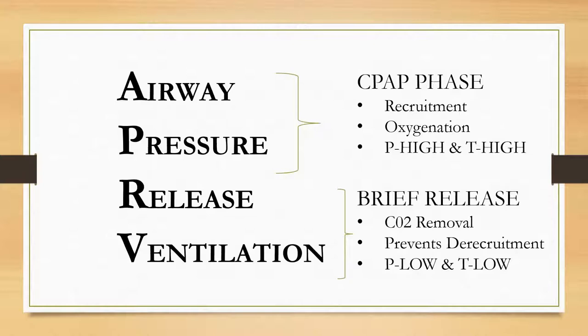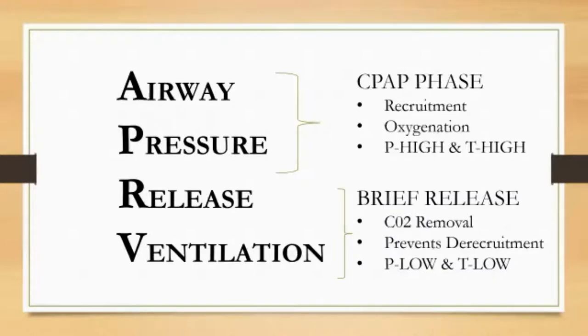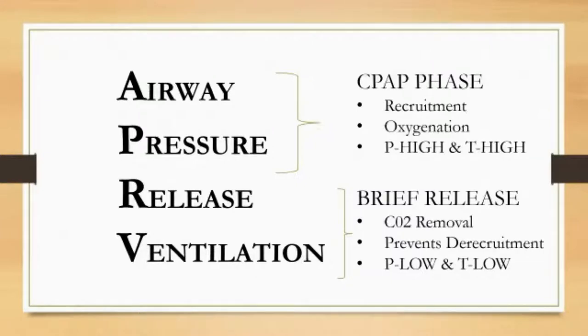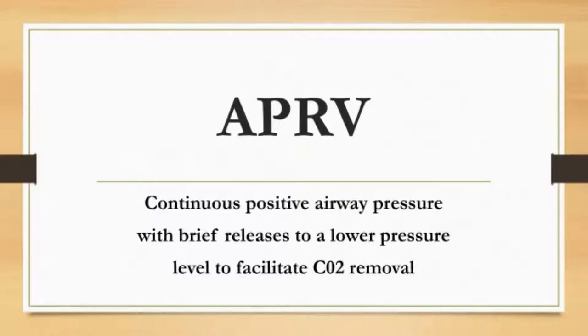When we look at airway pressure release ventilation, there are two aspects to this mode. There's the airway pressure — a CPAP phase that aids in recruitment of the alveoli and helps oxygenation. This CPAP phase is controlled by settings called P-high and T-high. There's also the release ventilation aspect, which is a brief release from the P-high setting to facilitate CO2 removal and prevent derecruitment. The pressure low and time low — referred to as P-low and T-low — control the release ventilation phase.